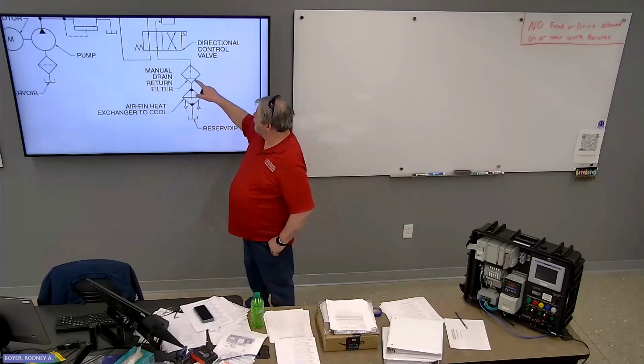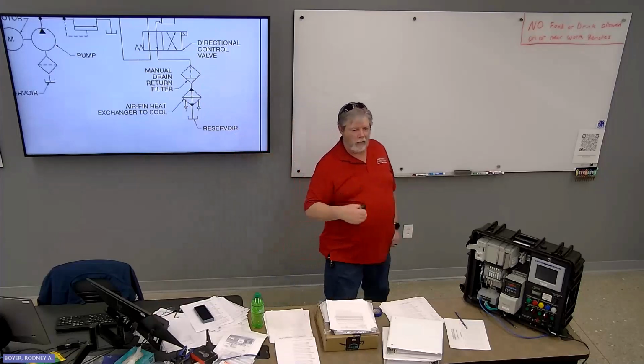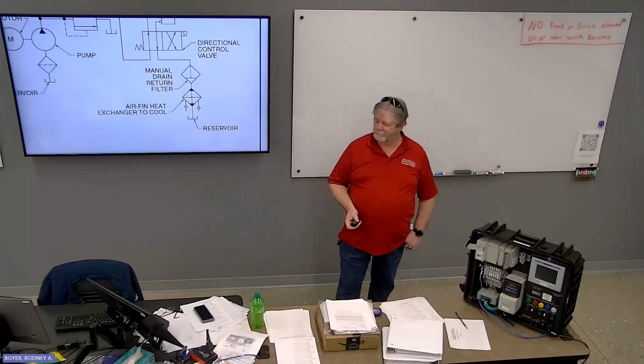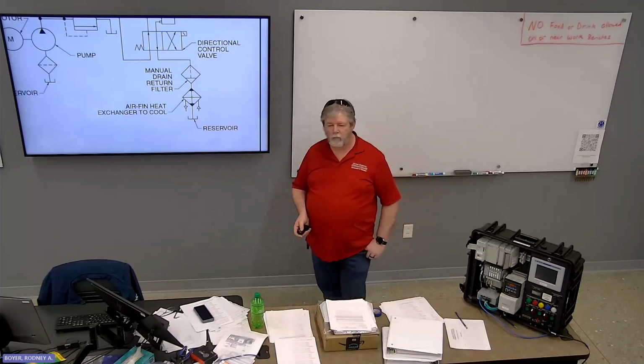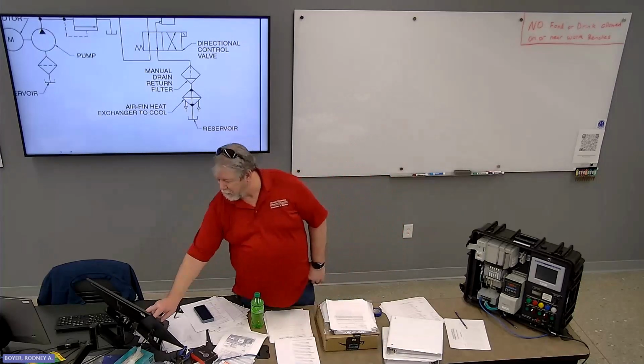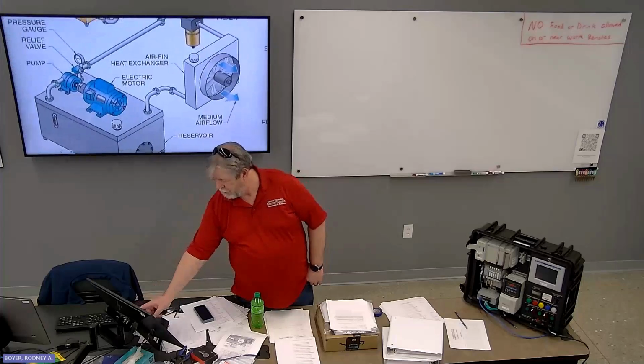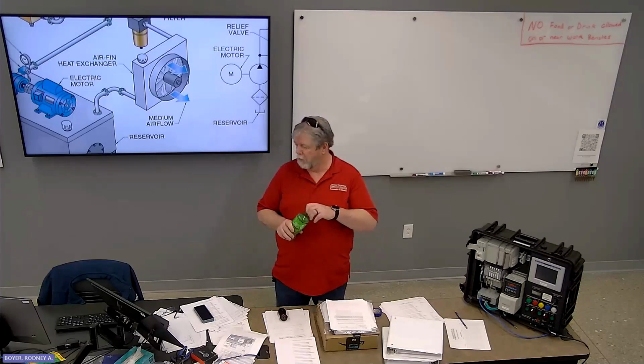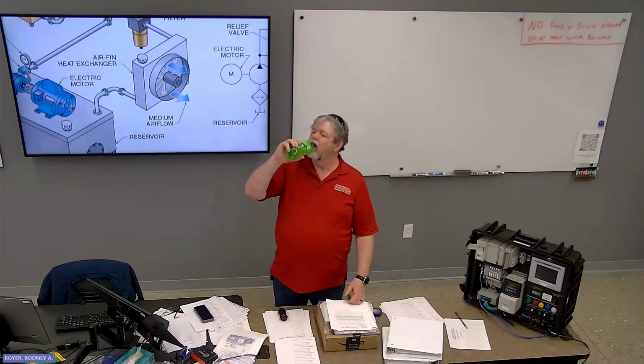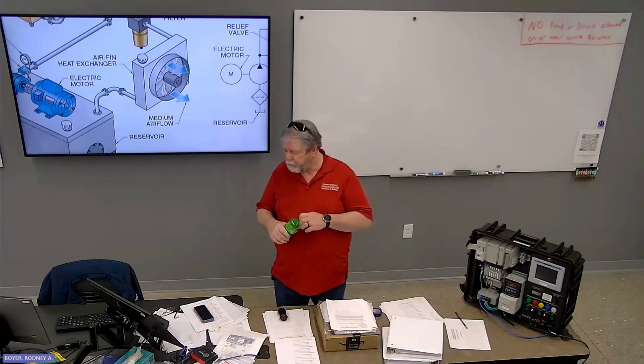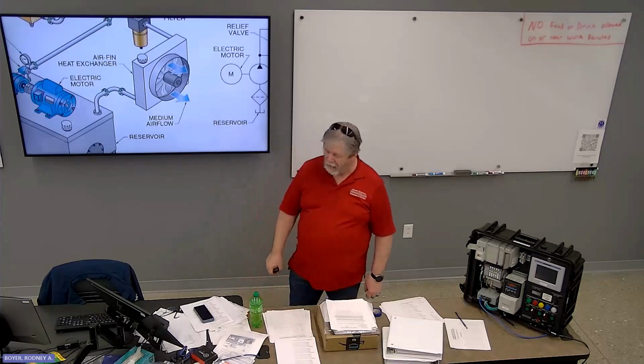So as the fluid is returning to the tank, it's going through the heat exchanger. It's going to try to remove some of the heat out of it, just like the radiator in a car does. Is the heat exchanger electrical power, or is it just? Well, that particular one is just a fan, so it would be. You could put a hydraulic motor on there and run it off the same power pack that the rest of the system is on too. That would work. Of course, that hydraulic motor would be a source of heat. It kind of defeats the purpose. Because it depends on how much heat you're able to remove.